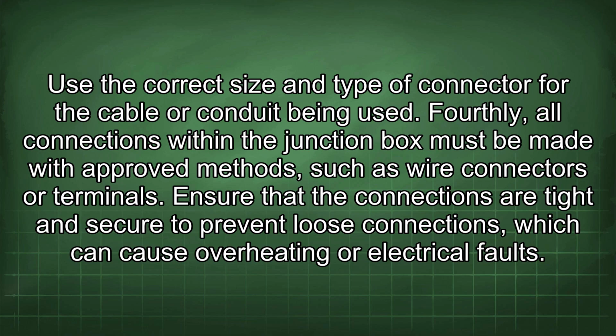Fourthly, all connections within the junction box must be made with approved methods, such as wire connectors or terminals. Ensure that the connections are tight and secure to prevent loose connections, which can cause overheating or electrical faults.